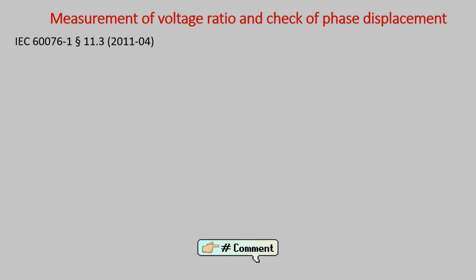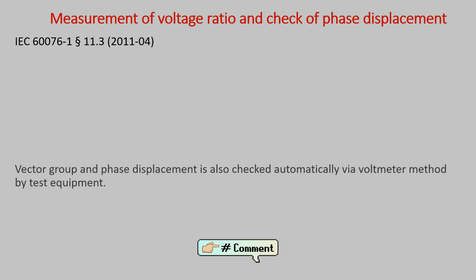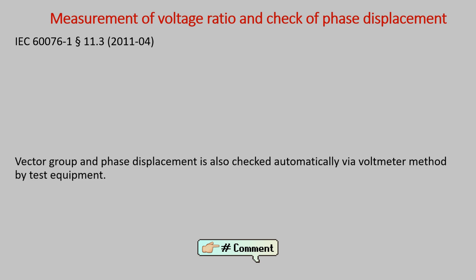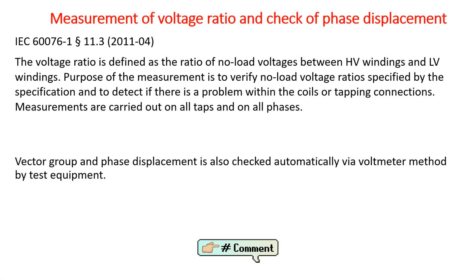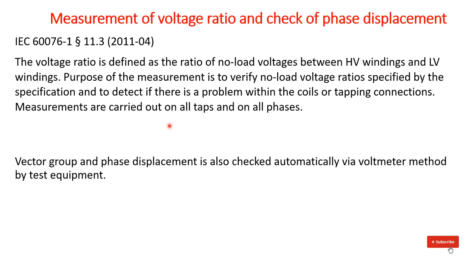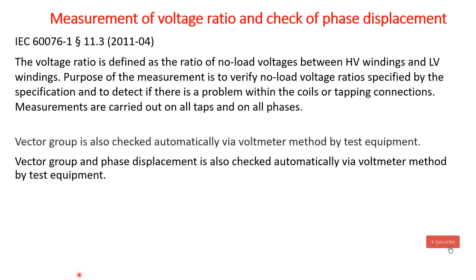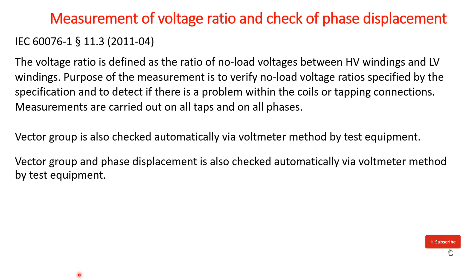As per IEC 60076-1, vector group and phase displacement are also checked automatically via the voltmeter method. Voltage ratio is defined as the ratio of no-load voltage between HV winding and LV winding. The purpose of the measurement is to verify the no-load voltage ratio specified by the specification and to detect any problem with the coils or tapping connections. Measurements are carried out on all taps of all phases, and the vector group is also checked automatically via the voltmeter method using this equipment.